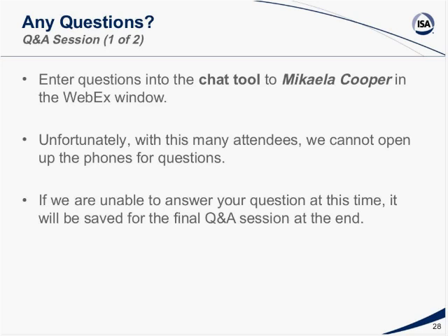Okay, thank you. Next question. Is it recommended to bypass any SIS protection in any situation with certain precautions? I'd have to look really close at the code. Under no conditions are you normally permitted to bypass any of your safety interlocks during normal operation. In other words, your safety shutdown, your safety alarms.